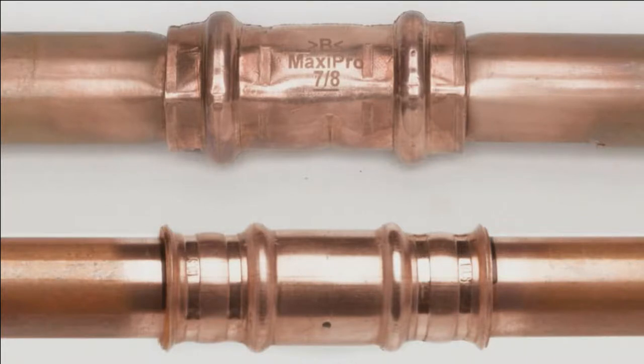You have to cycle it hundreds of thousands of times for the fatigue part, but where press fittings fail is the strength side. You rapidly push it up from zero to 2,100 within a minute, and then it has to hold for a minute. So with any technology, you have to start with that side of the test because that's where you'll fall down.